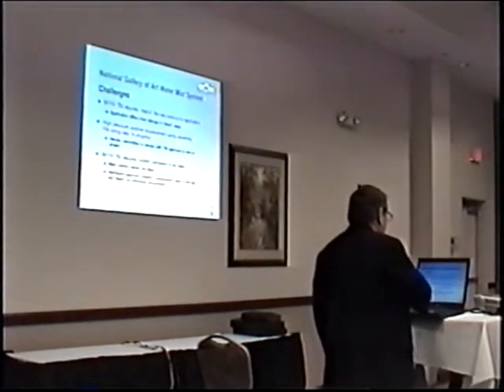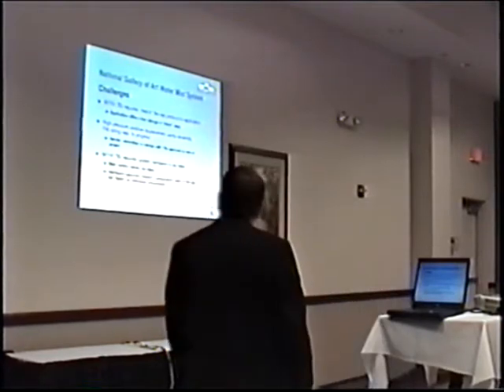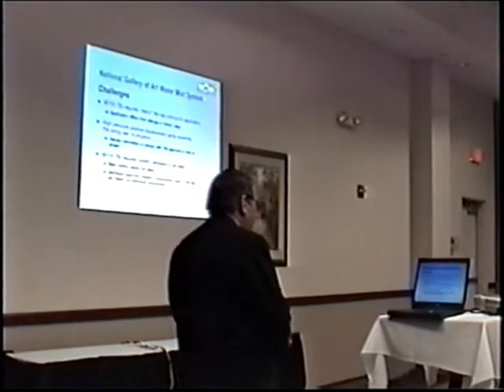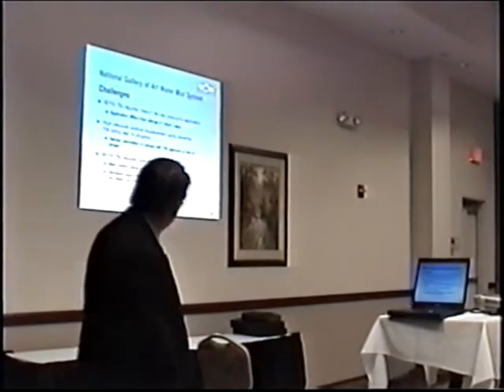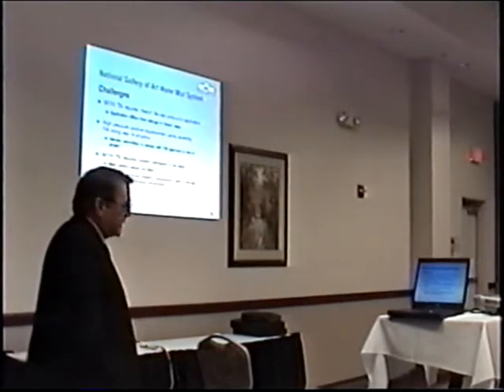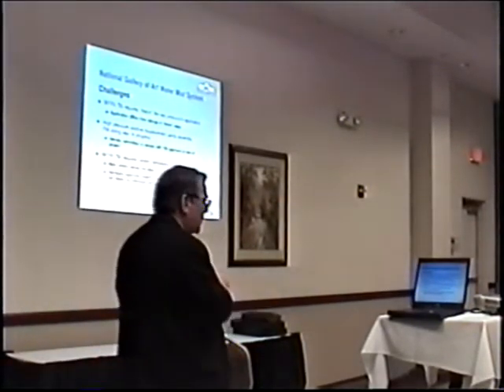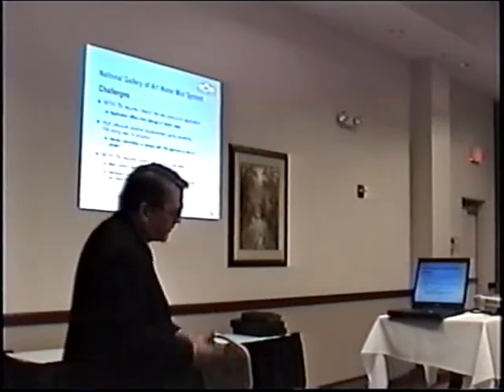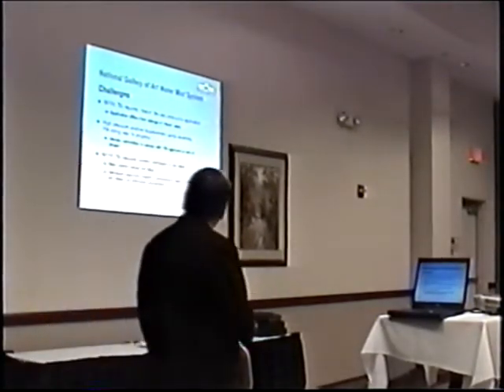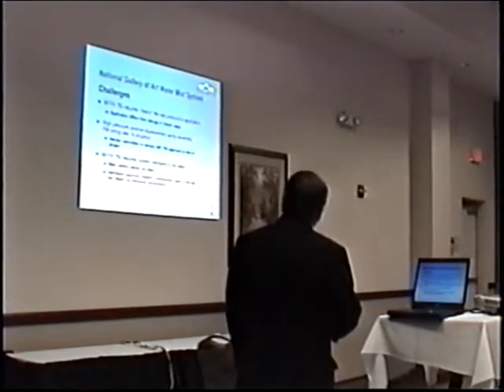So the challenges here, we have a general objective to meet NFPA 750, which requires that you match the fire test protocol to the actual application. And of course, you're never quite perfectly there. The fire test protocol didn't test combustible sealants, so automatically you're on to having to stick your neck out.